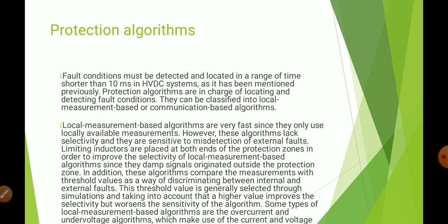If the fault current flowing is more than the threshold value, it is an external fault or an internal fault, based on the value we give. This threshold value is generally selected through simulations, taking into account that a higher value improves the selectivity but worsens the sensitivity of the algorithm. Some types of local measurement based algorithms are the overcurrent and undervoltage algorithms, which make use of the current and voltage.